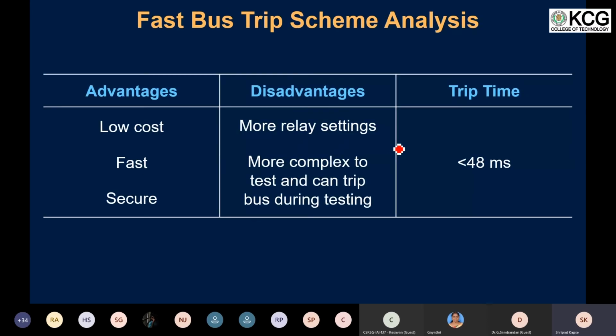instantaneously. But in this case, some of the disadvantages are that more relay settings are involved, the system is a bit complex, and there is a threat of cyber attacks as well if they are all communicating on the Ethernet network. The trip time associated with this type of scheme is also about 48 milliseconds, and in addition to it you would have the breaker operating time. If you add both of these, we may get a fault clearing time of about 100 to 120 milliseconds, and this kind of delay can also allow large arc flash incident energy to occur.